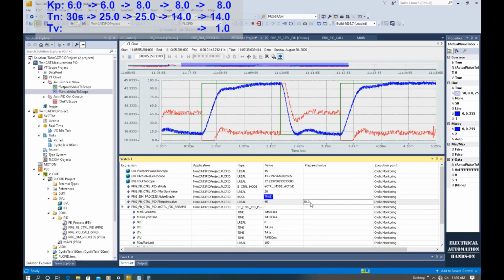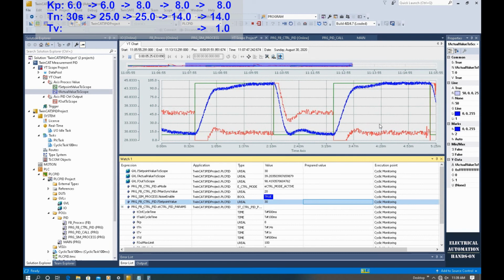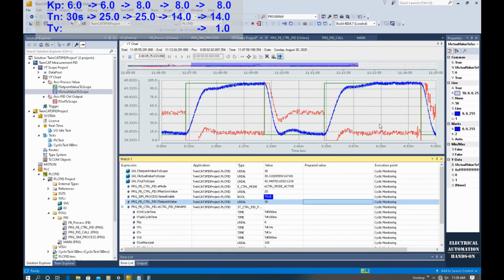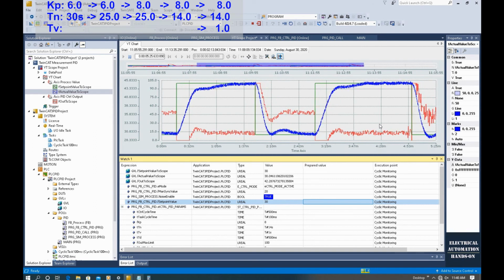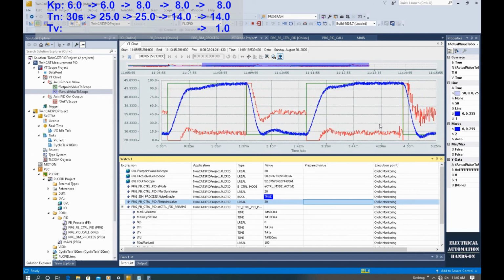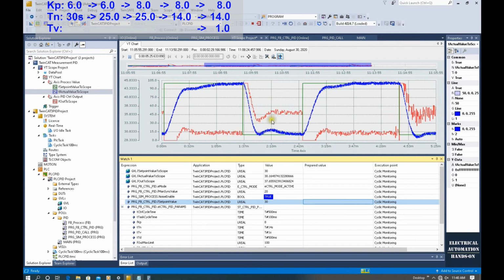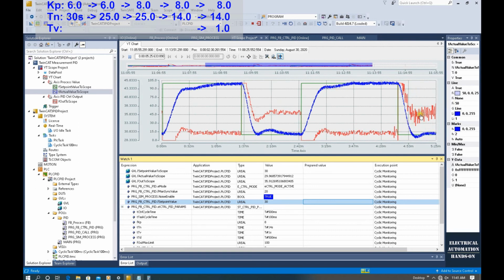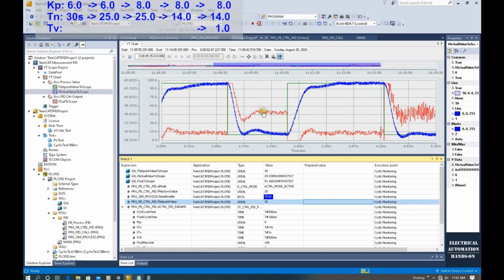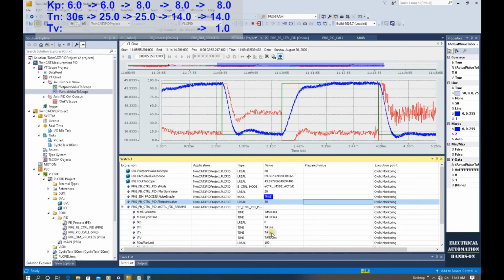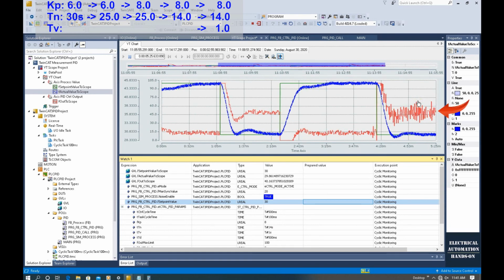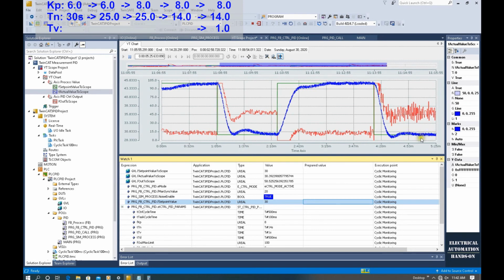And the set point, let's set to 30 and watch this process change. So comparing these 2 times, when the system was running here, we didn't use the derivative. And now we are using the derivative at 1 second. And the PID amplitude change is much higher than before, because using this derivative makes the PID behavior much more proactive than before. The system reached its stable status.